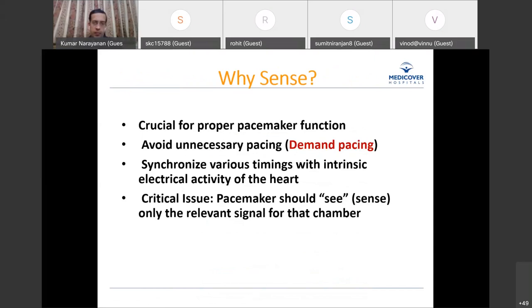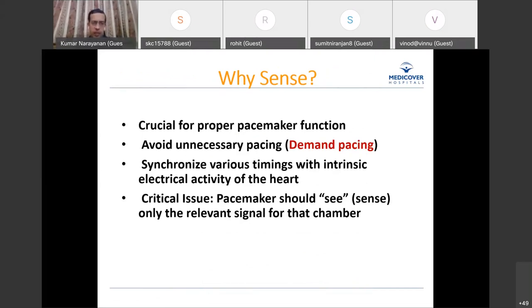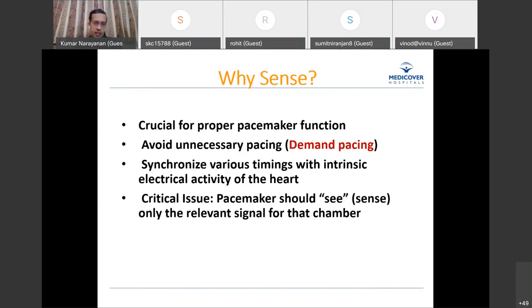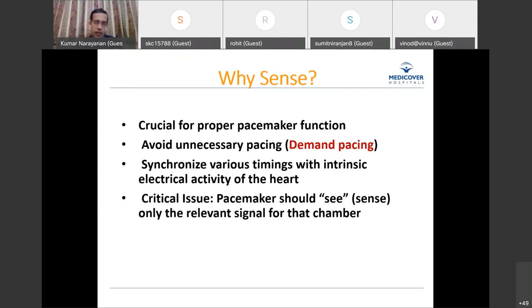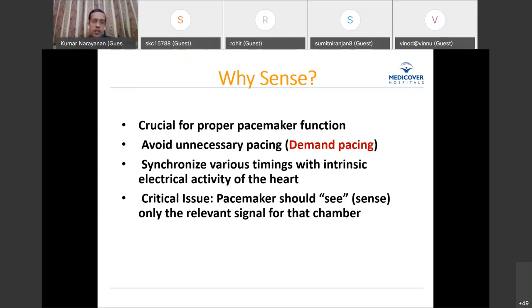Most pacemakers are demand pacemakers. It is important for the pacemaker to sense intrinsic signals appropriately so that it does not pace unnecessarily when the patient has their own intrinsic cardiac activity — for example, during intermittent AV block or intermittent sinus bradycardia. In multi-chamber pacing such as dual chamber pacemakers, all timing and synchronization depends essentially on proper sensing. The atrial lead must sense only atrial activity; the ventricular lead only ventricular activity.